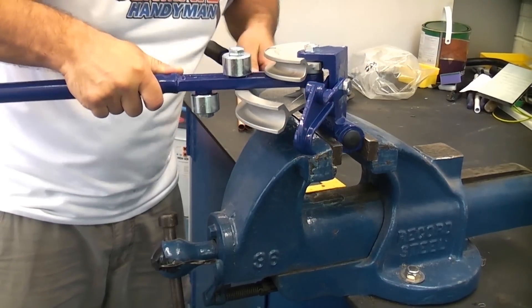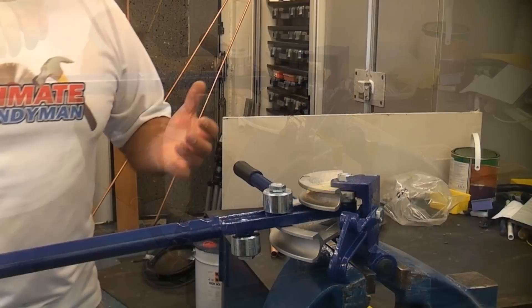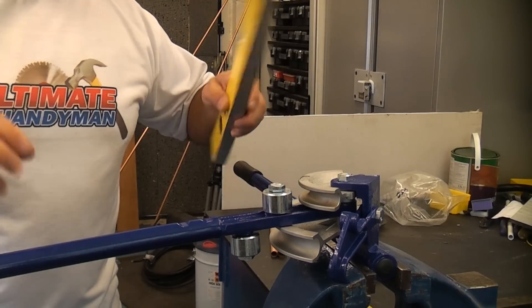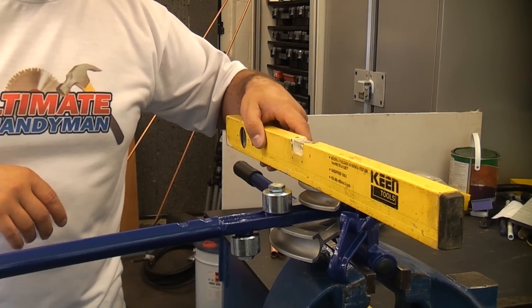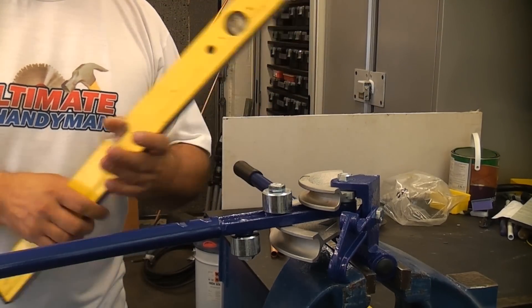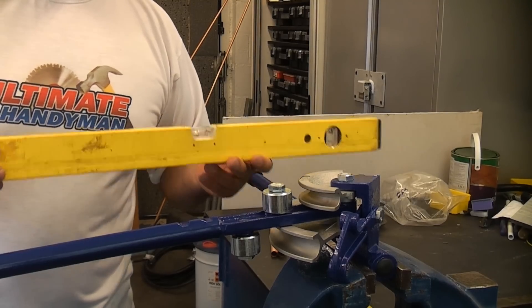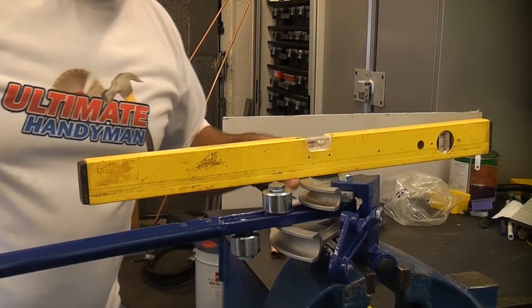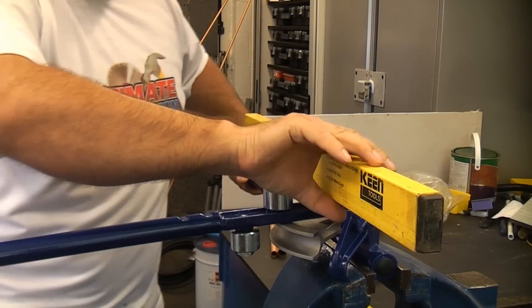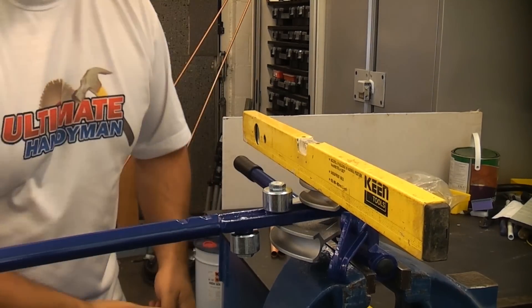I'm now going to put that in the vise and tighten up the handle. On this particular job it's not critical because I'm just showing you how to use the machine. But if you're doing quite a few bends it would be better if you actually levelled the machine off in the vise. If you get it levelled in both directions it is a lot easier doing bends, because instead of using the rake of the eye you can then use the spirit level to check that your pipe is straight.